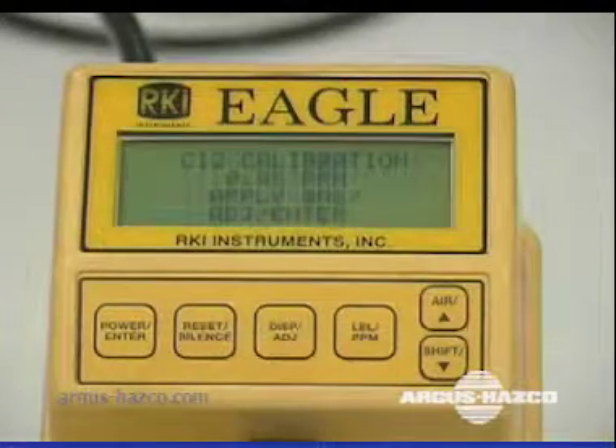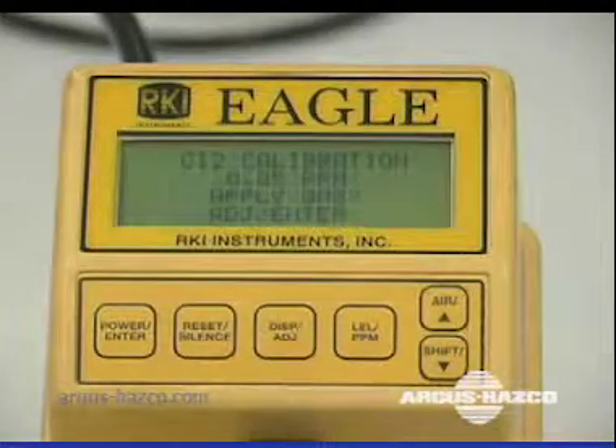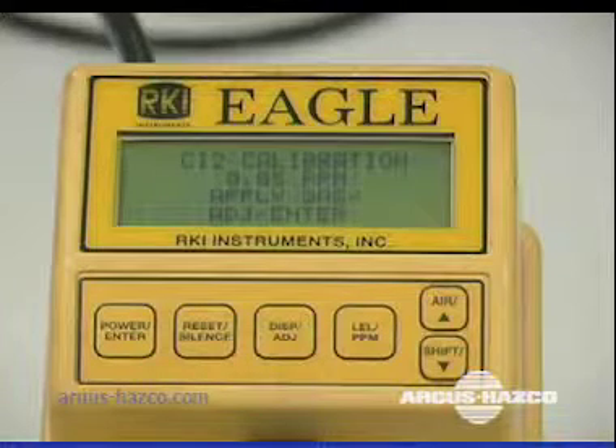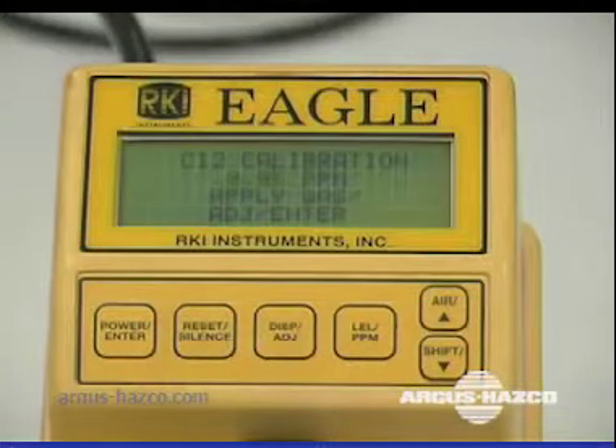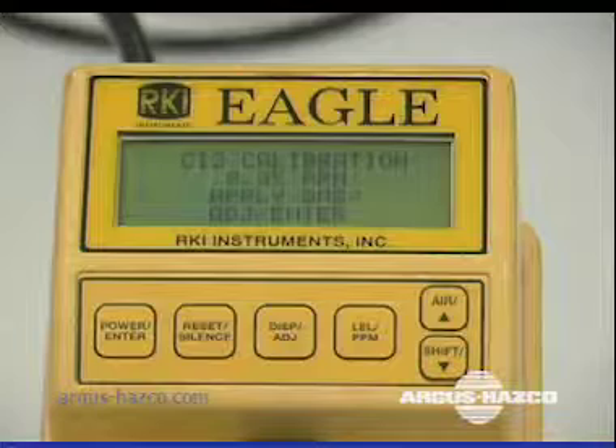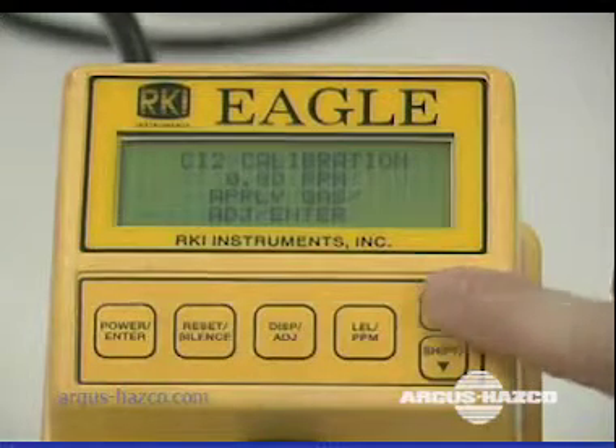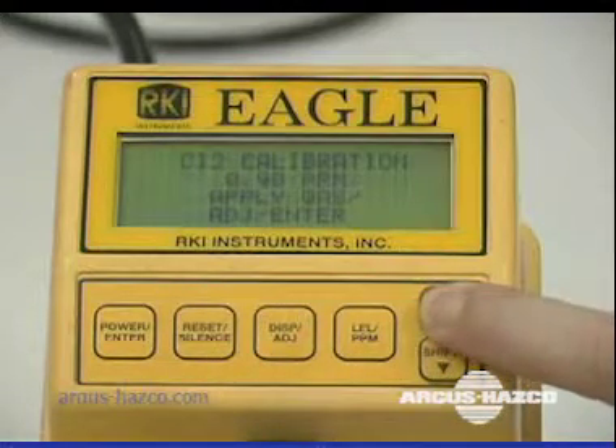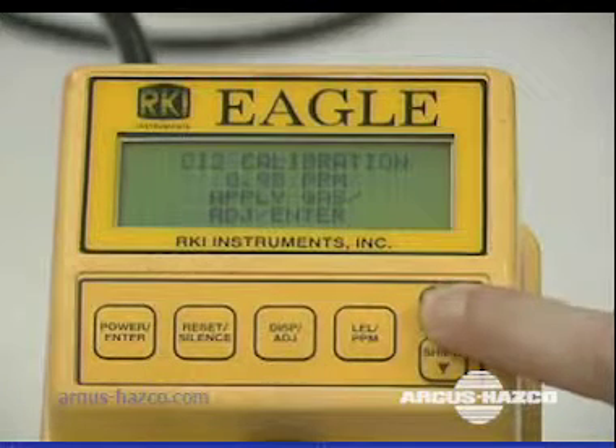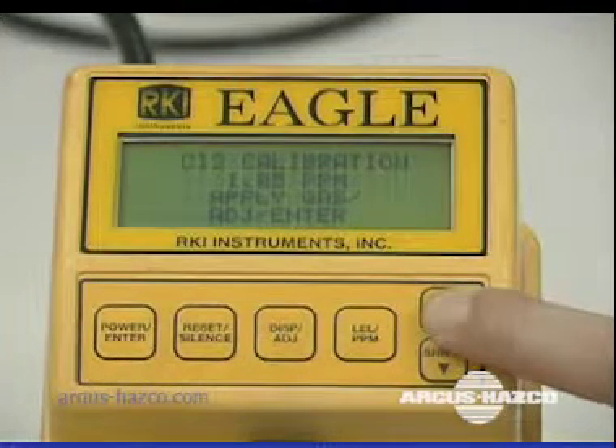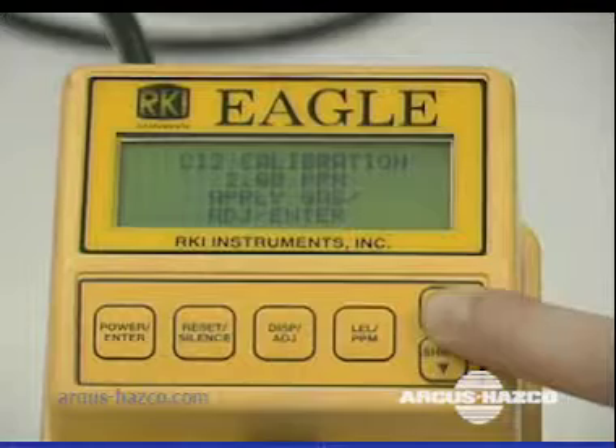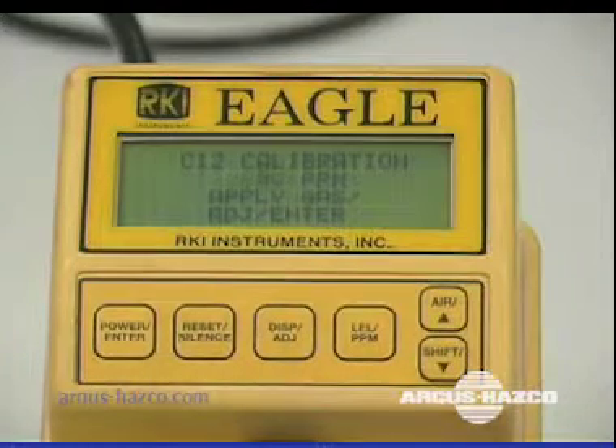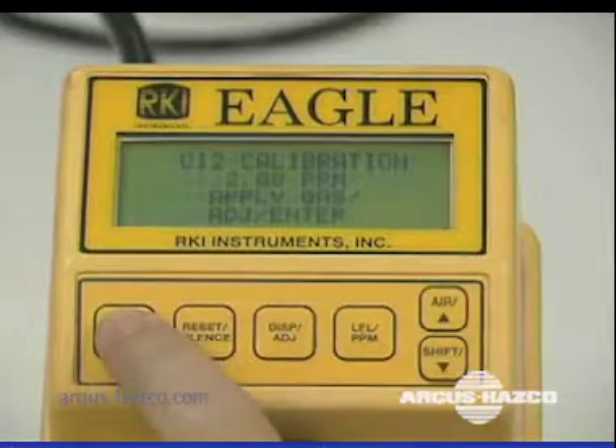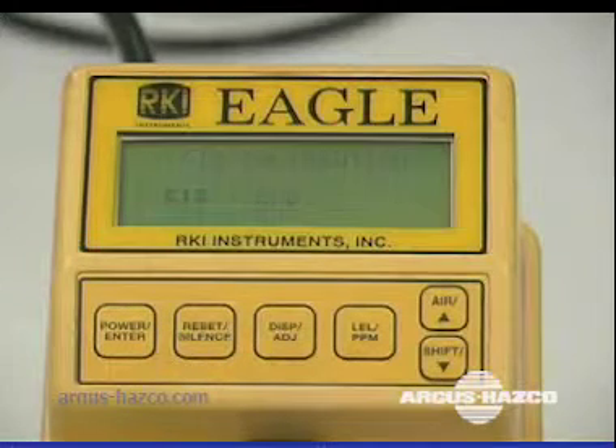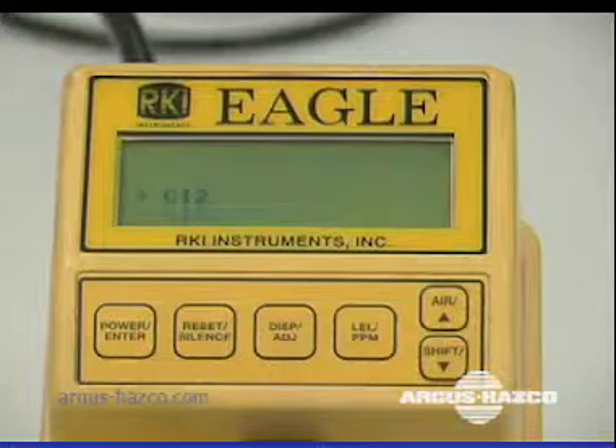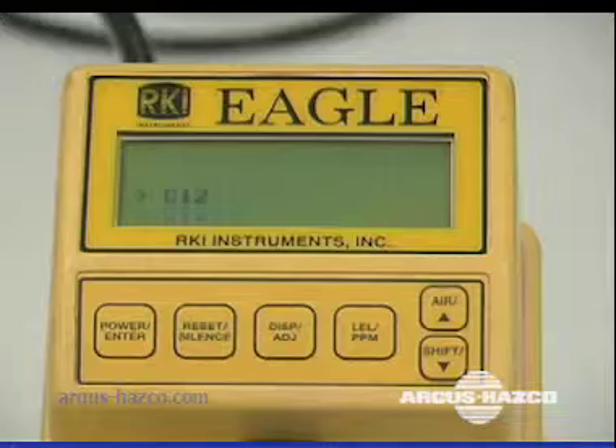As the gas is being applied to the instrument, allow approximately 2 minutes for the reading to stabilize. If necessary, use the up and down buttons to adjust the reading to match the concentration listed on the calibration cylinder. Press the Enter button to set the span value. The message Single Calibration End displays, followed by the Single Calibration menu.